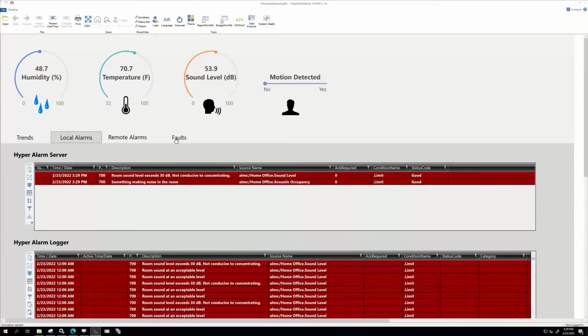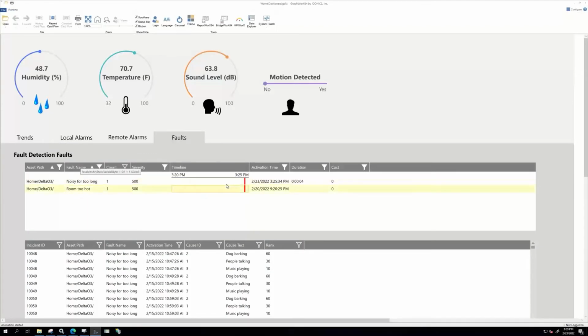My room too hot one is very similar. It just says if the temperature is greater than 15 Celsius for more than 15 seconds, issue a fault. So again, in this case, going back to the faults here, notice I'm getting a fault, and it tells me what time the fault started and how long it's been going on. You saw that in the IUOE example, where the facility had dozens of different faults defined against their different assets, and they were able to look at a page and say, what's in fault where.